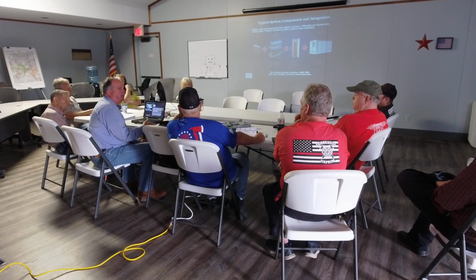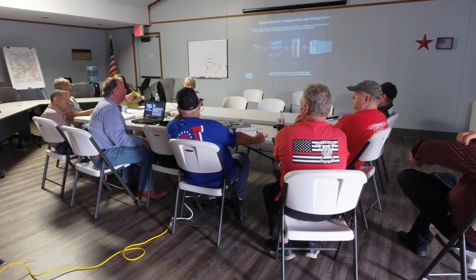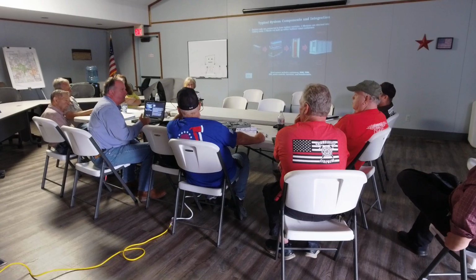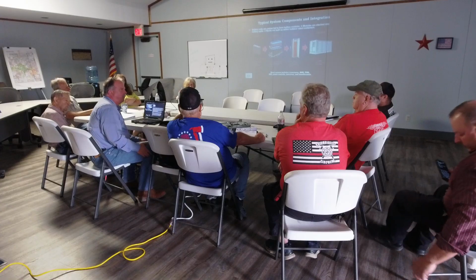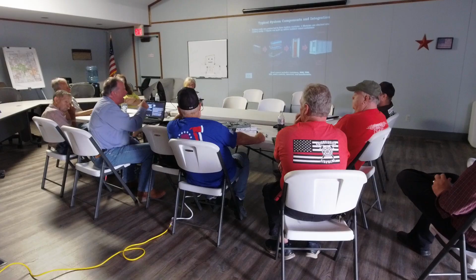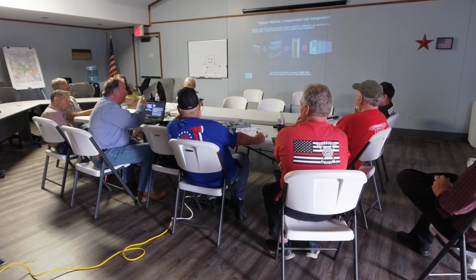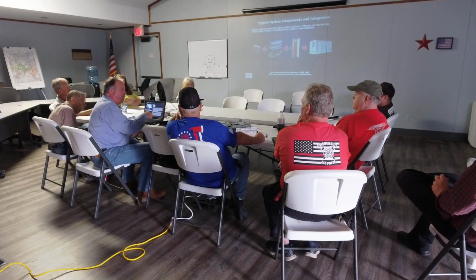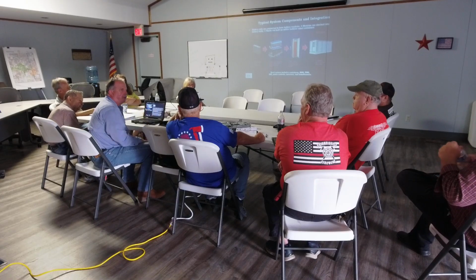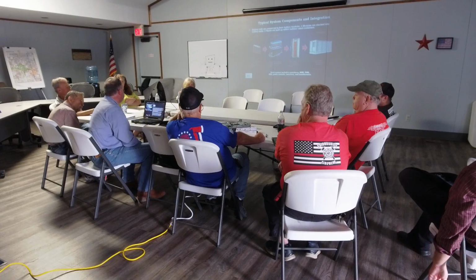Hydrogen dissipates rapidly, and in a lithium ion, or lithium iron phosphate, fire the gas is predominantly hydrogen. And so it's going to mix and dissipate and dilute very, very rapidly. And then we have our CO2 and our carbon monoxide. The thing is, when I train fire departments, there's nothing in that smoke that we don't already encounter in a residential structure. And here I can quantify exactly what it is because the manufacturer has to provide that information in their documentation. I am far more worried when I was running calls on a backyard shed fire because I had no idea what was in there.